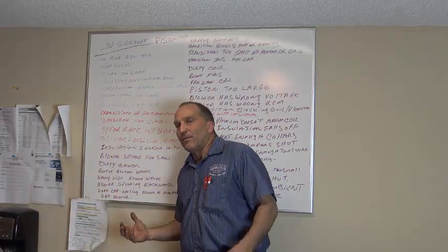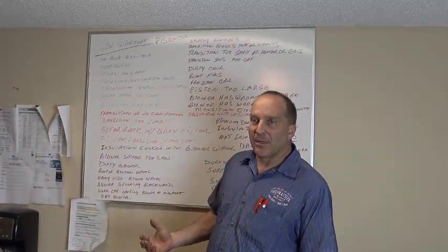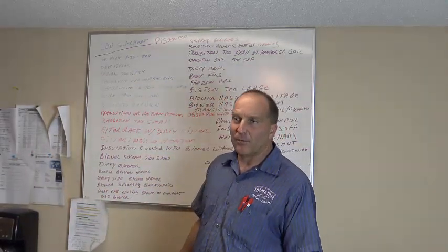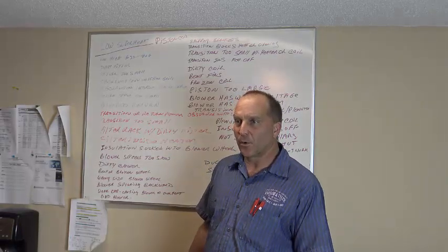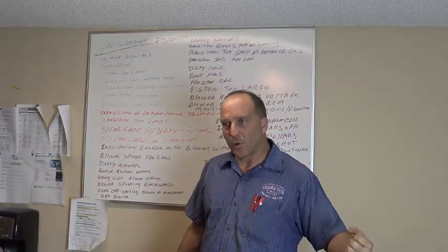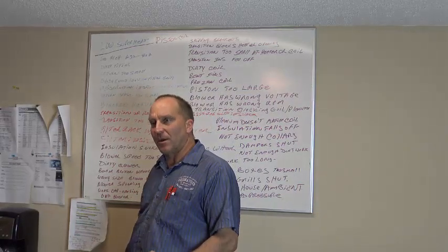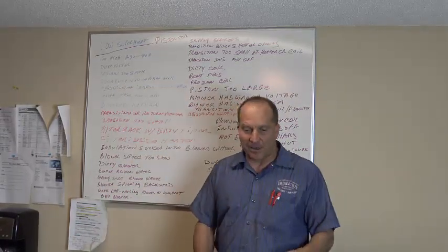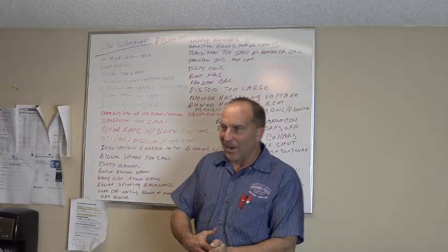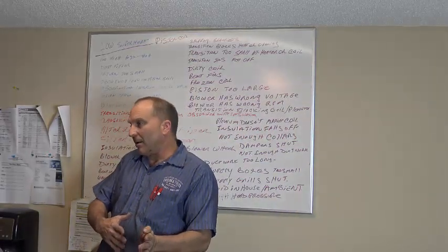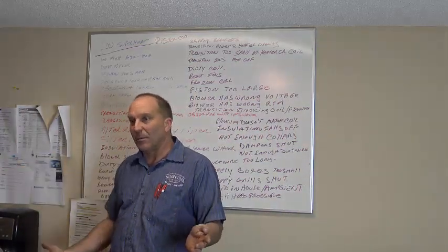If you have a very, very, very high static pressure inside your return, like a dirty filter or too small of a filter grill, or your chase is too small, that blower motor is sucking extremely hard trying to get that airflow through. So instead of a negative 0.3, you may have a negative 9, 10, or whatever may be the case.